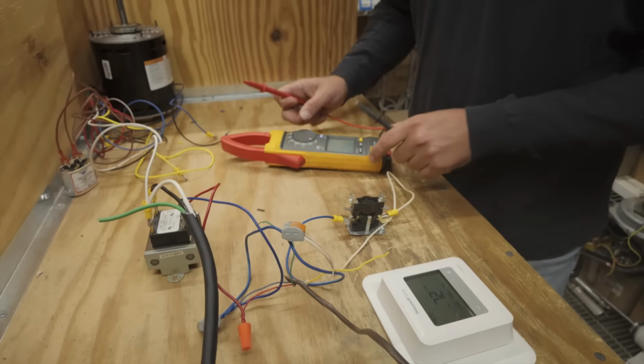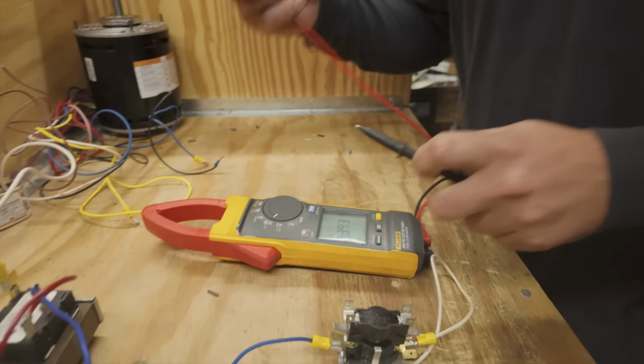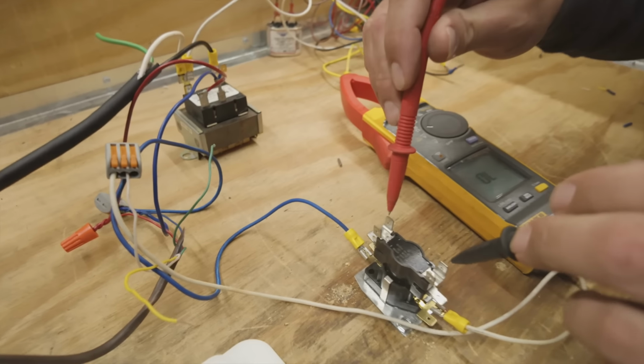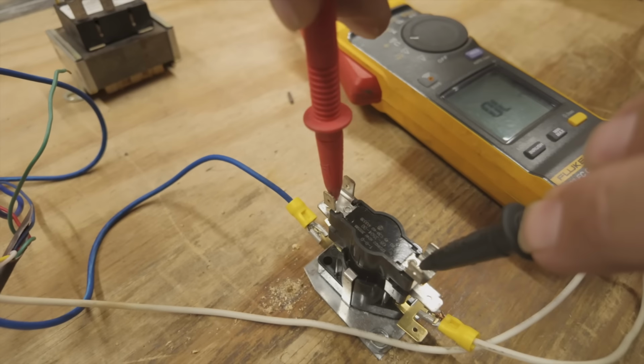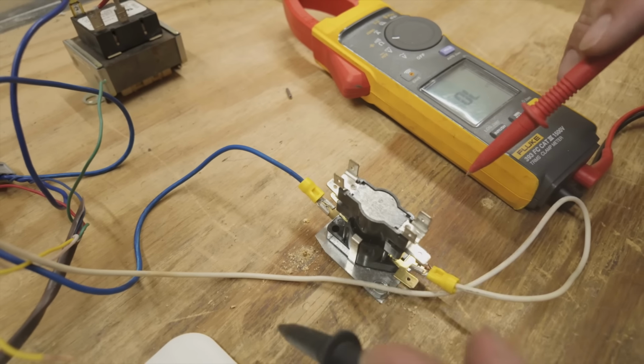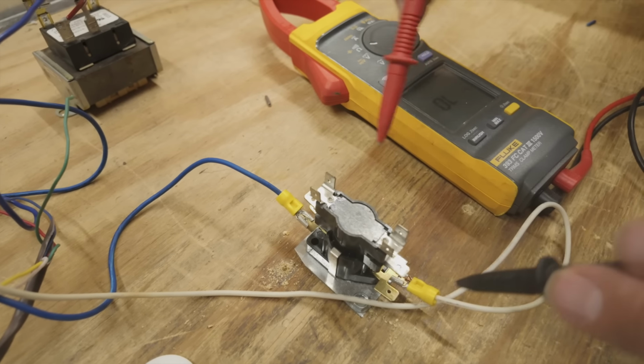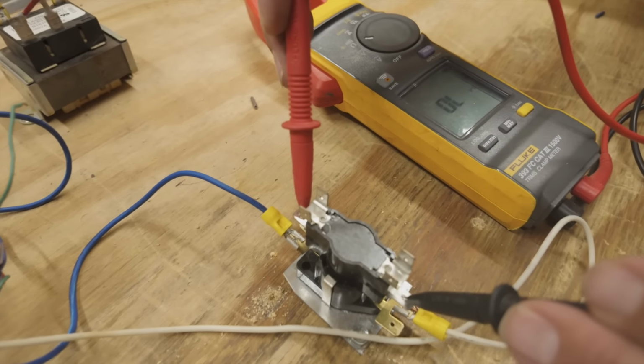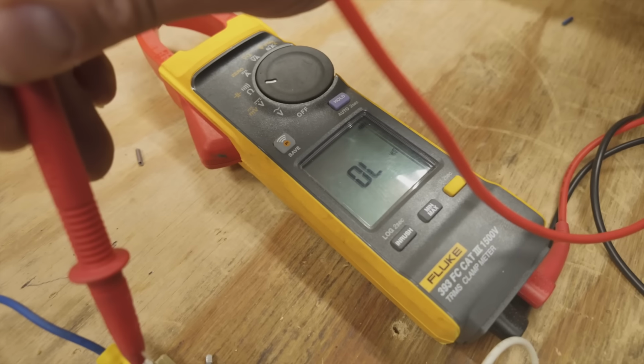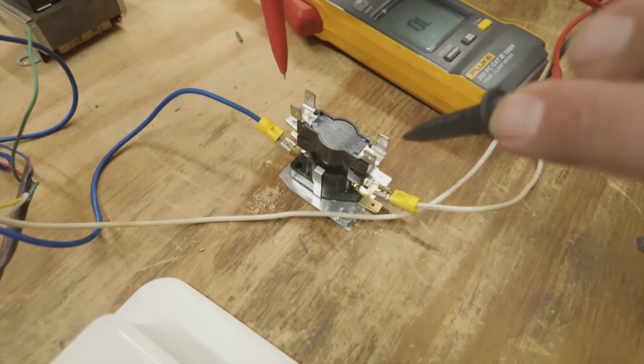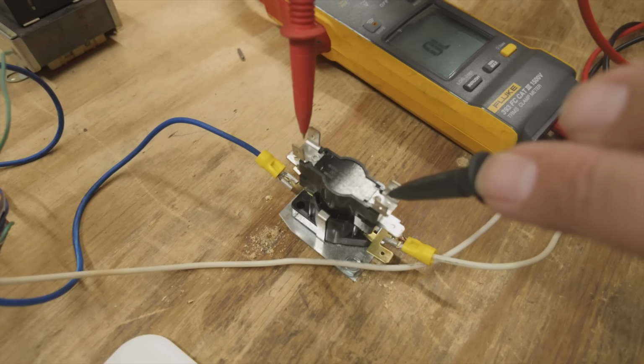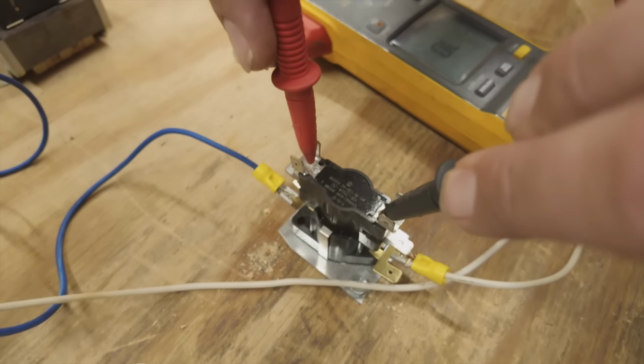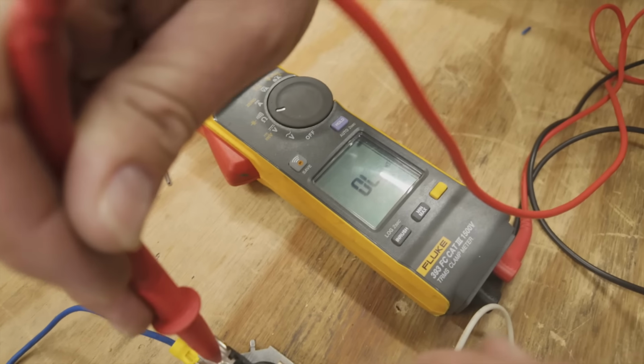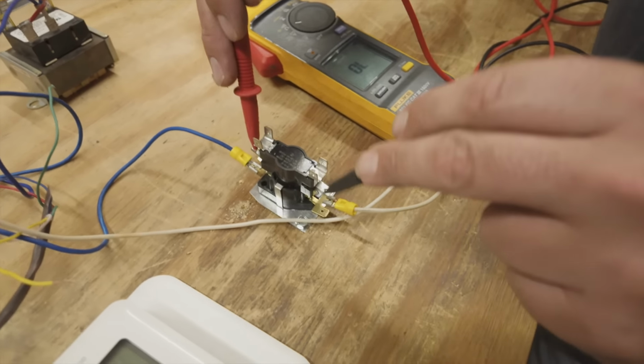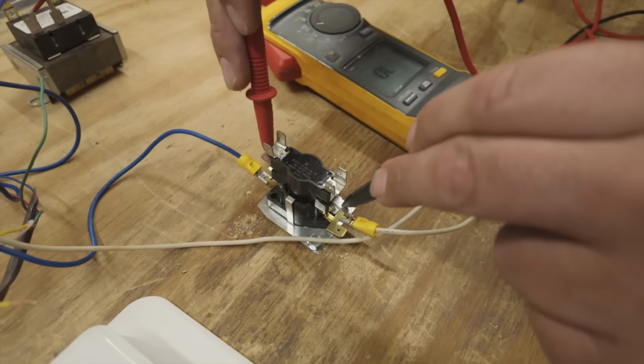Let's go ahead and check right now with our meter on continuity. What do we got? We got some contacts on top, and this is a single sequencer. Sometimes there are 2 sequencers, or double sequencers. So there's a set of contacts right here, and you can see it's OL, and that means it's an open circuit, open loop. And then on top, we've got another set of contacts, and it is normally open as well. So open circuit, normally open.